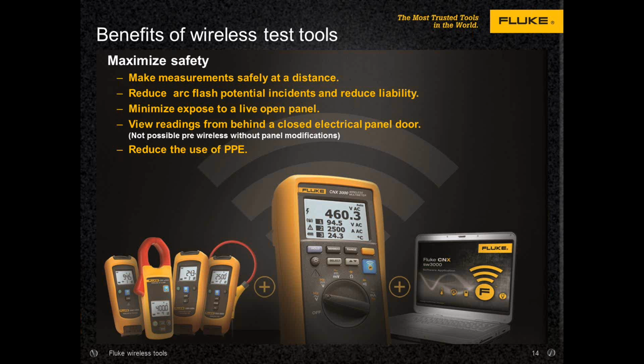Let's talk a bit about the safety aspect of wireless test tools. Today, with conventional tools and a meter, if you're working in high energy panels, because of the length of those test leads, you're standing right in front of all that energy. Up until a year ago, test probes could have three-quarters of an inch of exposed metal at the probe tip, and some of the spacing in three-phase panels is fairly close from phase to phase.